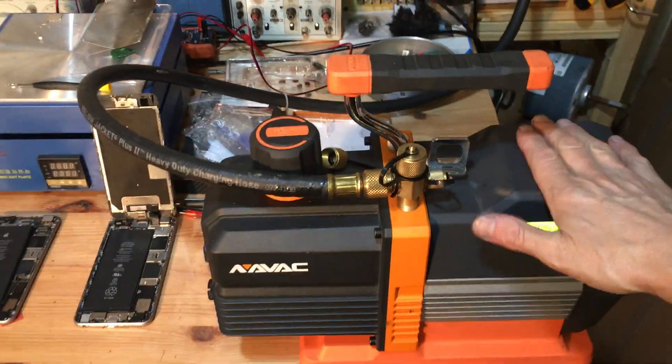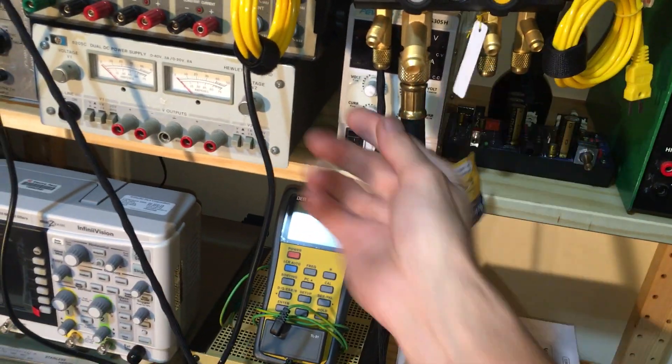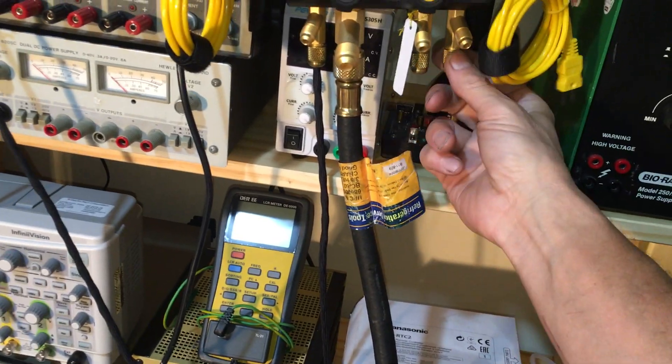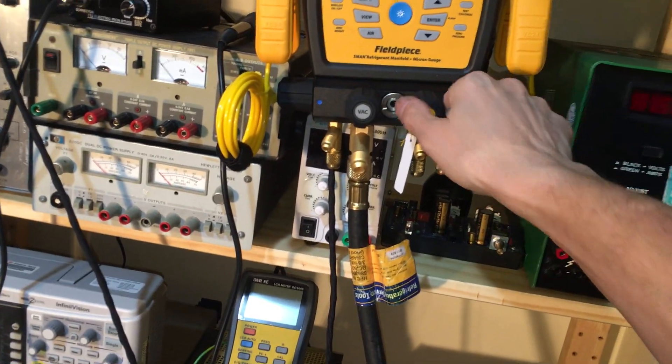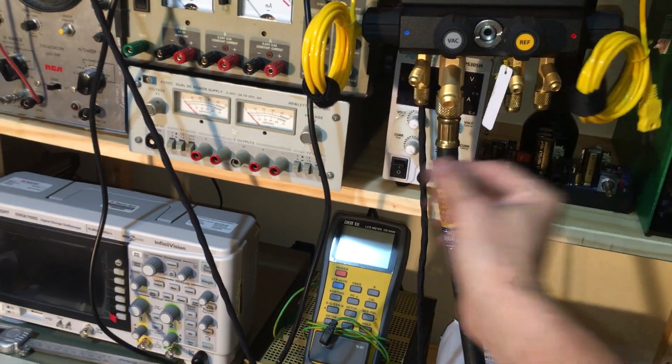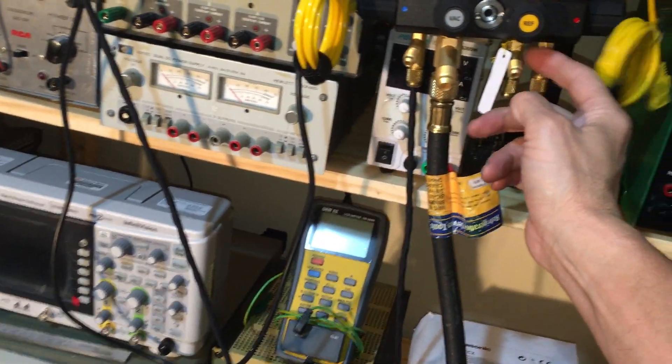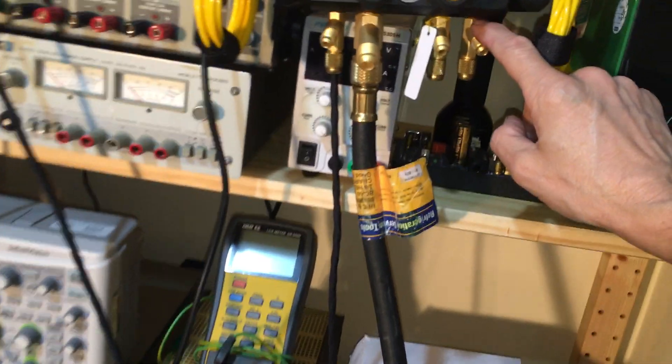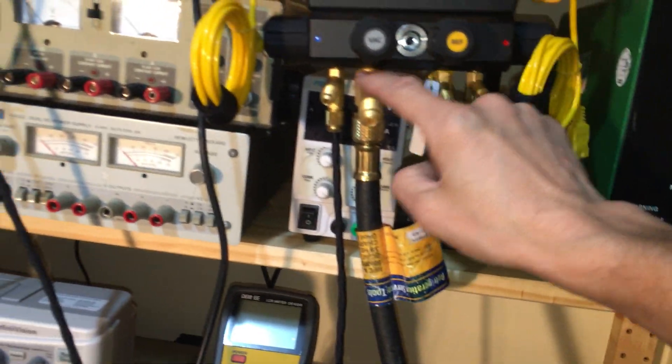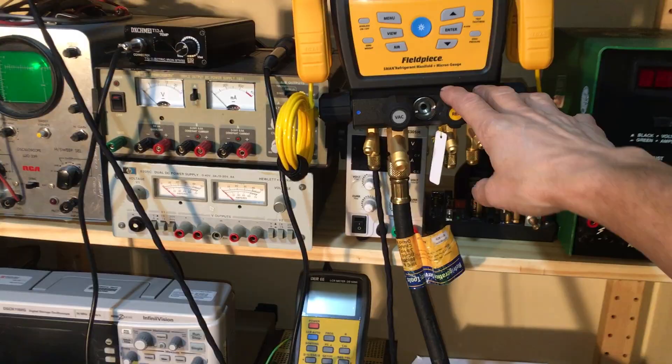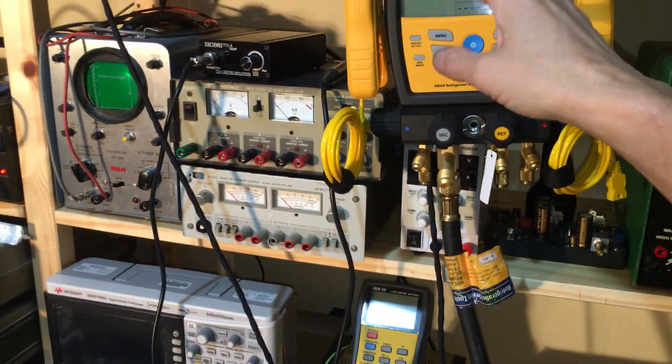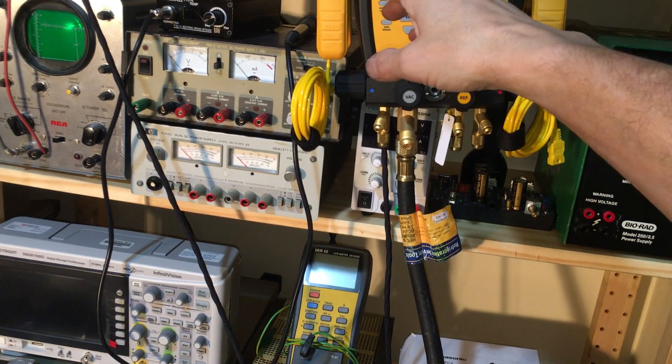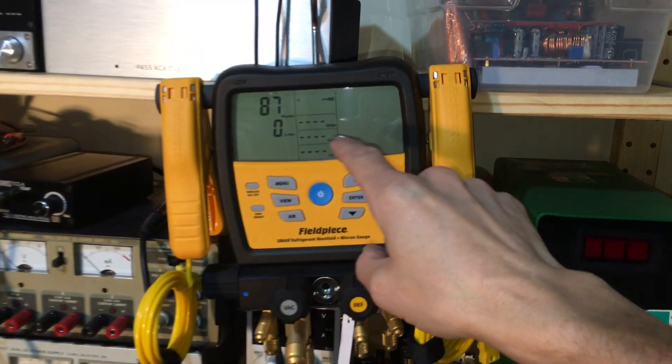So here's the story. The vacuum pump was running last night when I came home. You can see I have caps on the end here in case it leaked. I had the valves all the way open as if they were going to hoses, vacuuming out even the tubes to make sure there are no leaks anywhere. I came home and it was on the vacuum pump for about three hours, able to get down to roughly 140 microns of vacuum.